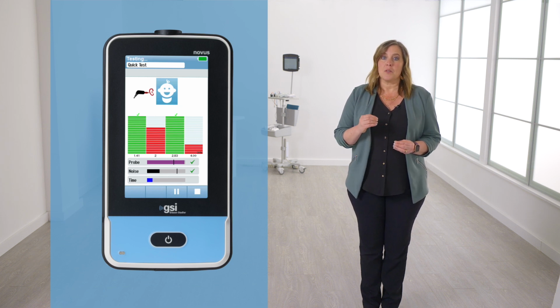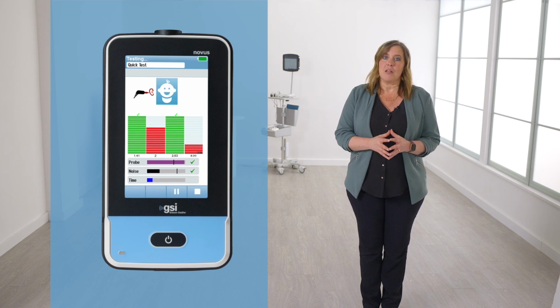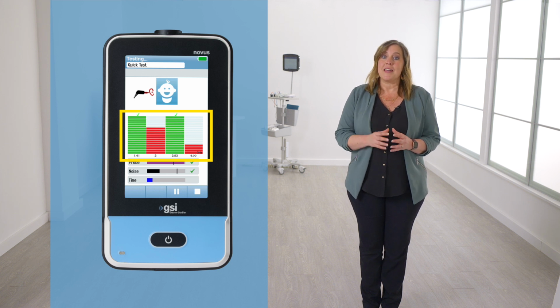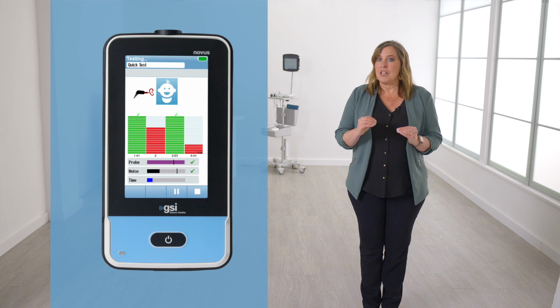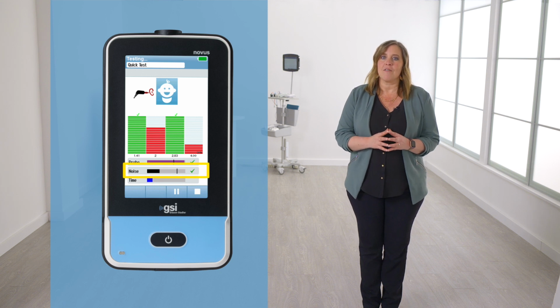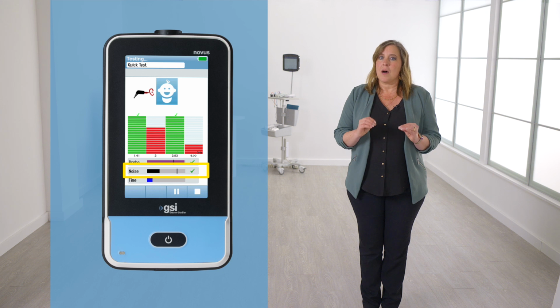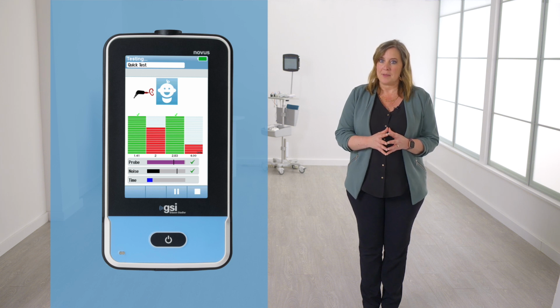The testing screen displays a few key pieces of information to observe. Bar graphs in the center of the screen will show the progress of each test frequency toward a pass result. The red bar indicates the right ear and the blue bar indicates the left ear. When a frequency has passed, the bar will turn green and there will be a check mark indicating a pass result for that frequency. A horizontal noise bar with a green check mark indicates that the noise is not interfering with the evaluation. It is possible to pause the evaluation to reseat the probe or to address environmental noise and then continue the test when conditions become stable again.